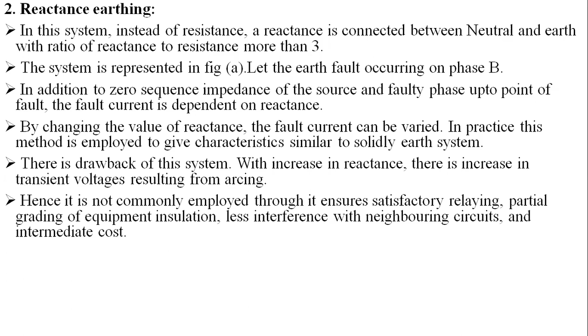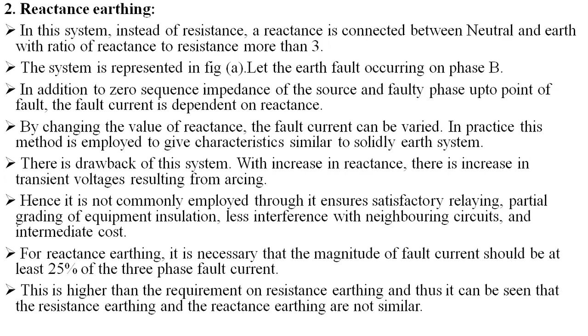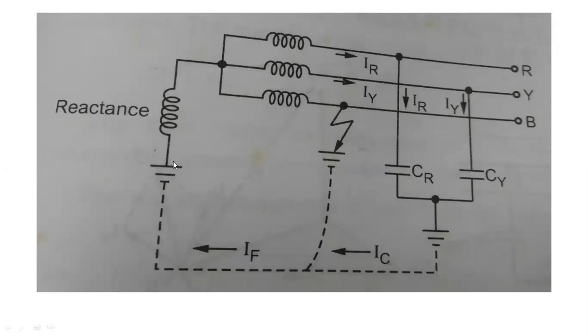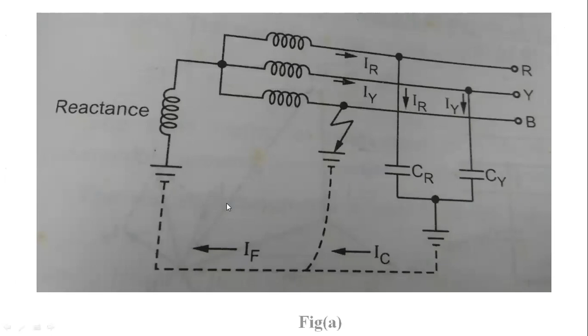So for reactance earthing, it is necessary that the magnitude of the fault current should be at least 25% of the three-phase fault current. This is higher than the requirement on resistance earthing, and thus it can be seen that resistance earthing and reactance earthing are not similar. Between the neutral and the earth, we are going to consider the reactance, which is not similar to our resistance.